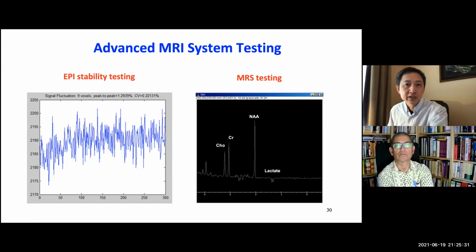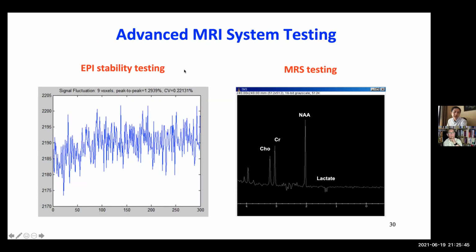The last test is about advanced MRI system testing. Just to give two examples, this is not done everywhere. The EPI test basically looks at stability. This is an important sequence for diffusion, perfusion, and functional MRI, so if your scanner is running these exams, we recommend looking at the stability. Spectroscopy also is not run on all scanners, but if your scanner is running spectroscopy, then we recommend scanning a spectroscopy phantom. You can see the typical peaks, choline, creatine, NAA, and lactate from the phantom.